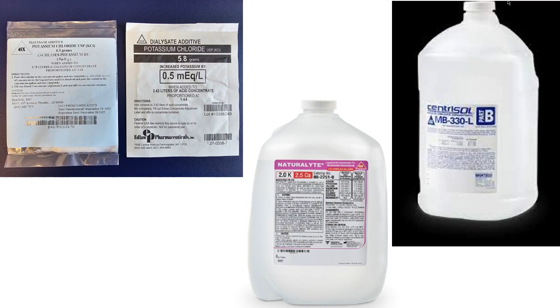Potassium changes it. If you were to increase potassium by 2, you won't see it in your conductivity panel. It will not change. The greatest contribution to your conductivity is what? Sodium. Yeah. So the small changes in your potassium, calcium, buffer, yes. If you were to increase your buffer solution, what happens to the conductivity? Does it increase or decrease? Conductivity decreases because it's a buffer. So if you increase bicarbonate, your conductivity will be lower, not higher.